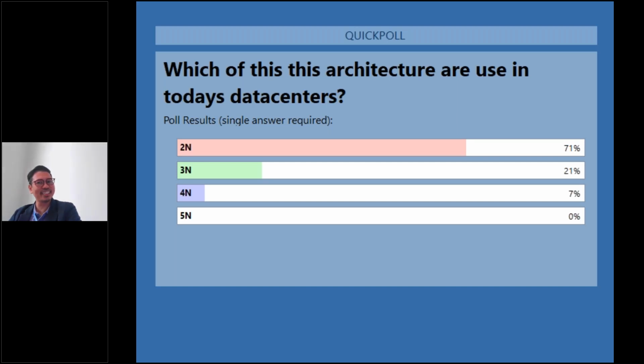My biggest challenge there is synchronizing all the UPS, all the system sources, because when you do transfers, you need to synchronize. And with synchronization, you have an issue with the reference because you have 4 references. So we need to make sure that they are referencing into one. But again, you are right, majority are still using 2N because it's the most easy to implement.